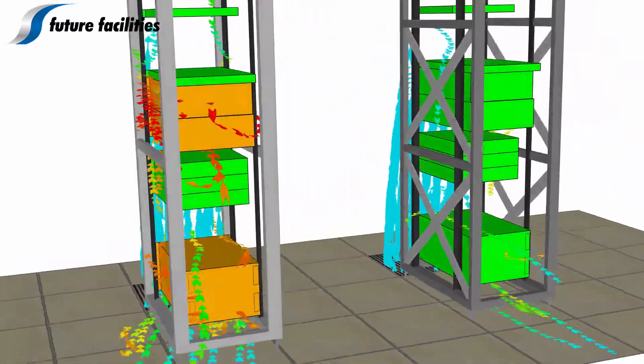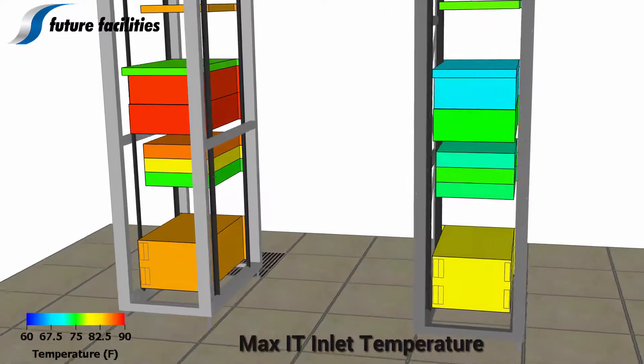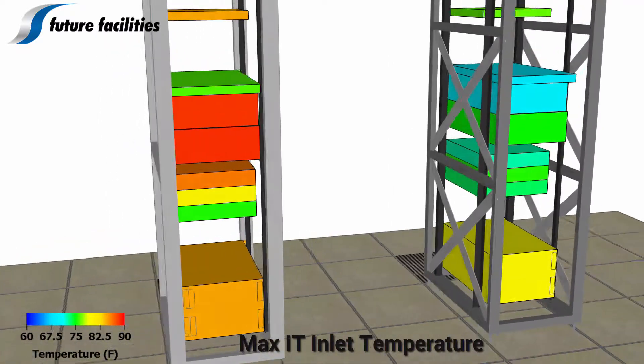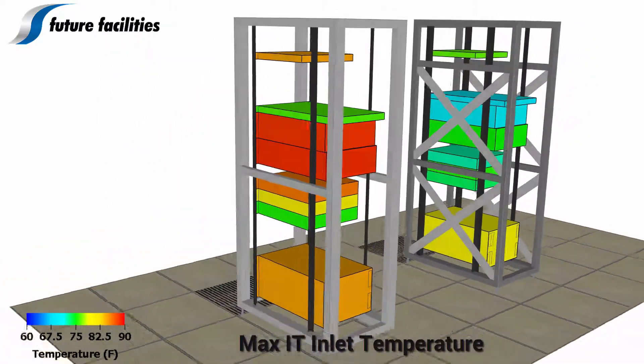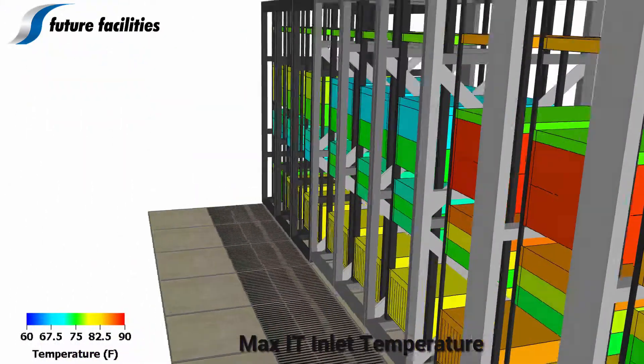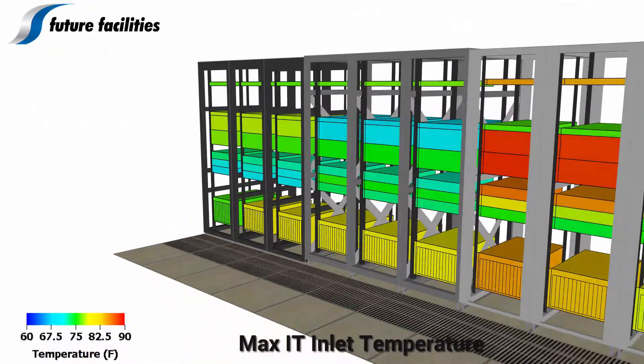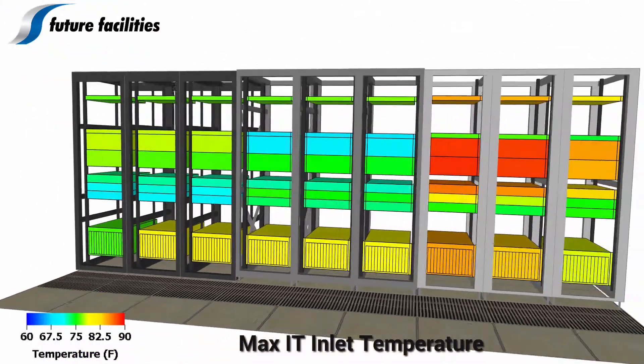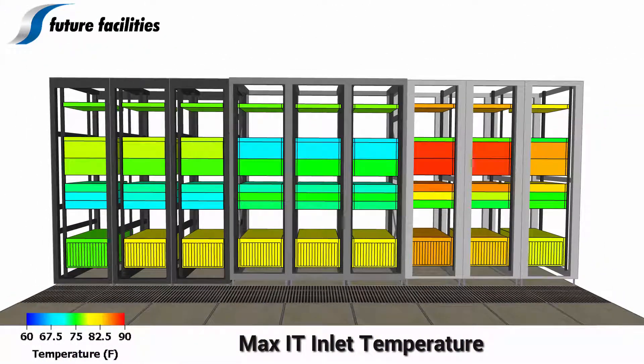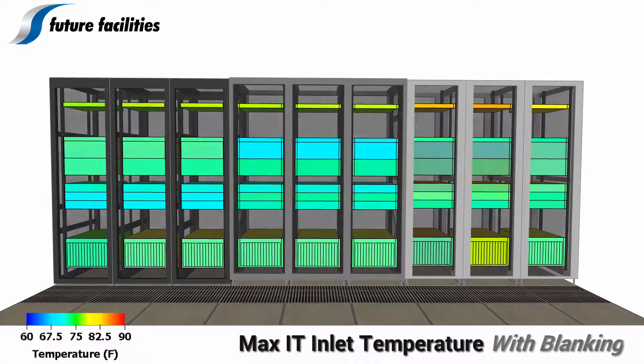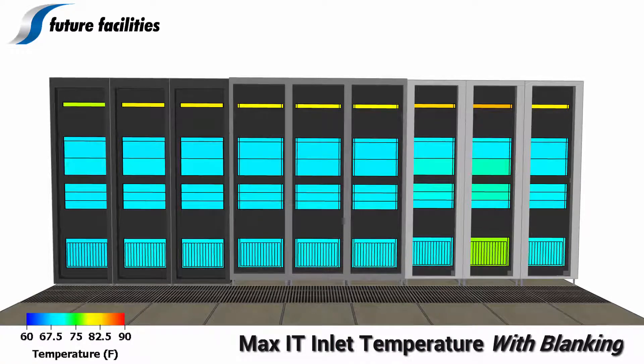Your sales team can leverage this information to show potential customers how your product performs compared to the competition. Changing the plot type to maximum inlet temperatures provides more insight into the thermal performance of each cabinet. It should be noted that even when blanking the empty U slots, there are higher inlet temperatures in the cabinet on the far right.